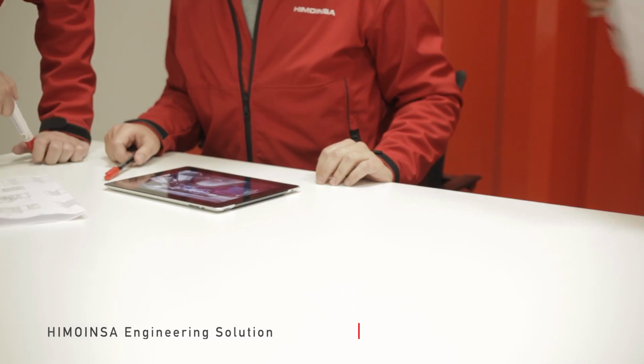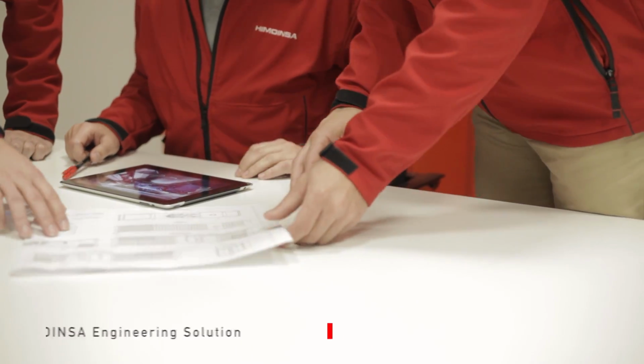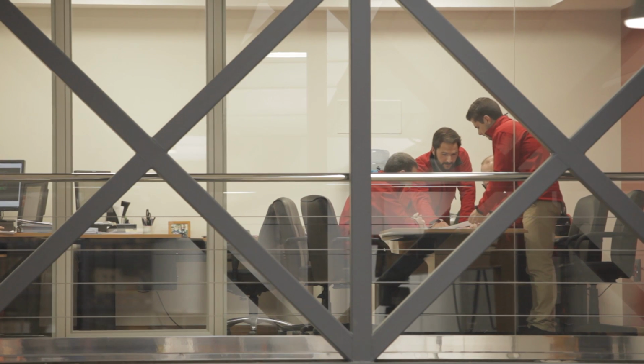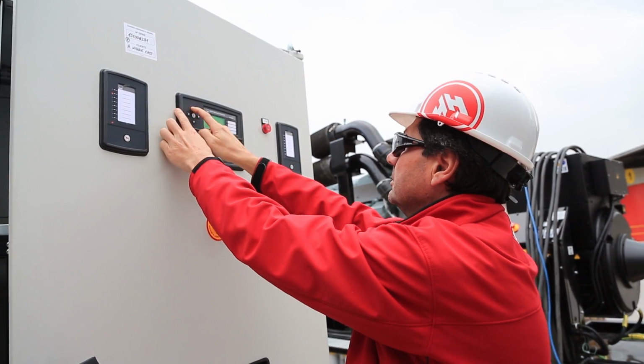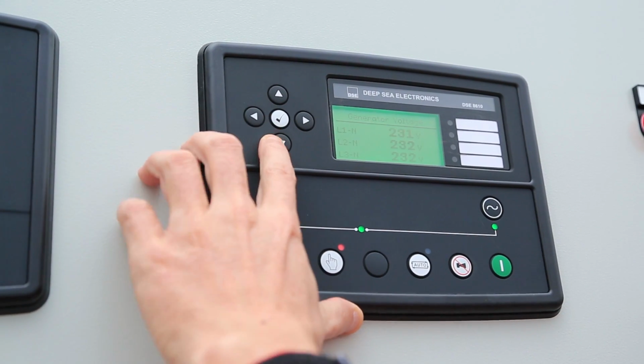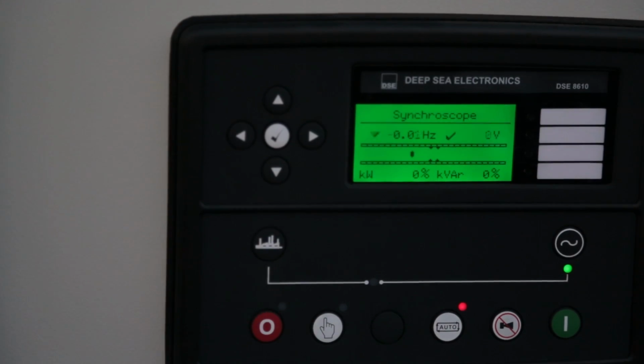FAMCO and Himoinsa needed to meet the stringent requirements of Qatar Civil Defence. What we needed to do was prove that all gensets would start from a dead start, synchronise and produce power within 10 seconds. We managed to show this by the factory witness test, where we achieved 7.8 seconds, and we also proved the same on site.